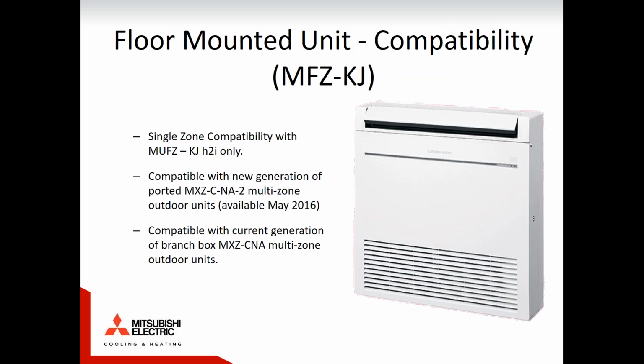In terms of compatibility, guys, the C generation multi-zone systems on the branch box end, C generation is perfectly acceptable. That's all you need to be aware of. The only thing you need to be cognizant of is, and I believe Pierce Phelps has rotated inventory at this point, to integrate a new floor console on a port type multi-zone system, you need to have a version NA-2. It needs to be a -2 port type model to integrate the new floor console unit.